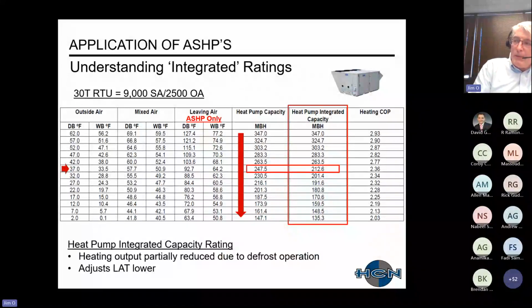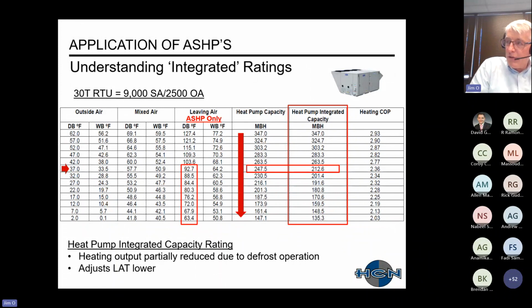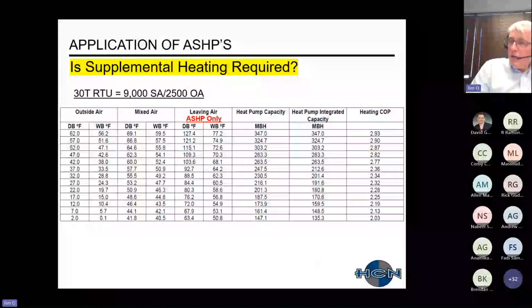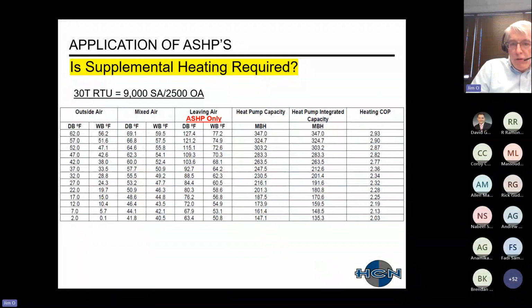What the integrated heating capacity is doing is partially reducing your leaving air temperature, your capacity, due to the defrost operation. So what ends up happening is we end up adjusting our actual leaving air temperature. The chart here is reflective of the integrated heating capacity of our air source heat pump. Now also, is supplemental heating required? Going back to our chart here, I'm going to tell you that probably almost always, right, Rick, we've done this every single time with auxiliary heat.